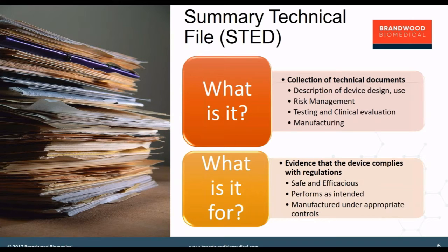The main purpose of the technical file is to demonstrate compliance of the medical device to the regulation. So in putting together this technical file, you will basically collate all the artifacts that are required to provide evidence of compliance to the regulation. So you'll be demonstrating that the product is safe and efficacious, performs as intended, and also is manufactured under the appropriate controls on your manufacturing side of things.